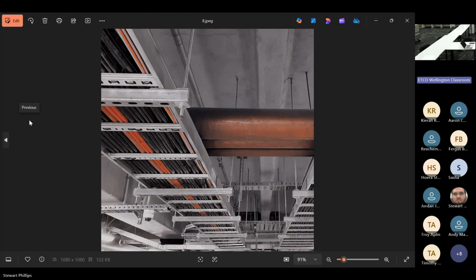So this is what we call cable ladder. It is not the same as cable tray. Cable ladder is used more for your big cables. As you can see, there's less material, so it's more cost effective. It's usually used for your big mains runs down through the main trunking of the building. So you'll find this coming out of switchboard rooms or running inside big main switchboard rooms. This would be the stuff going through the basement to the fire riser and then up the fire riser, bringing the mains to each floor.